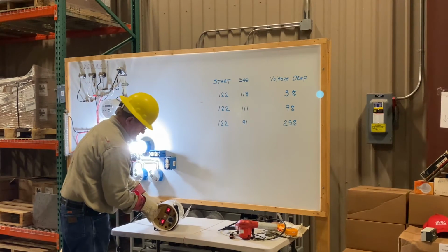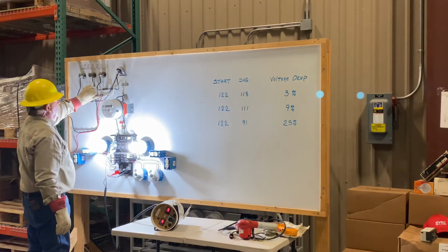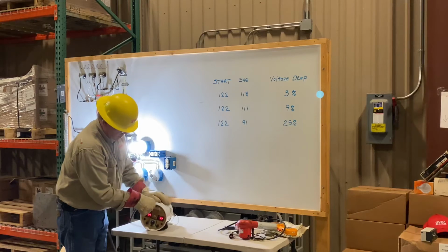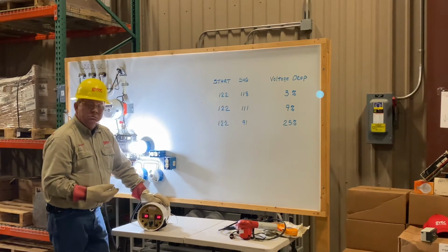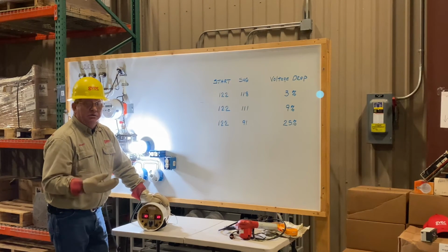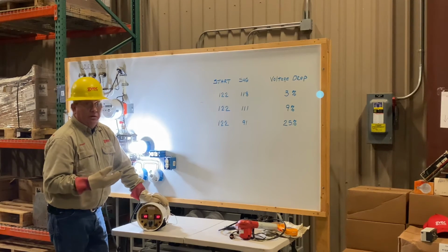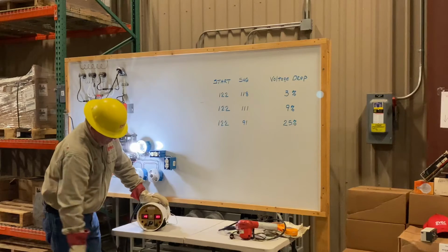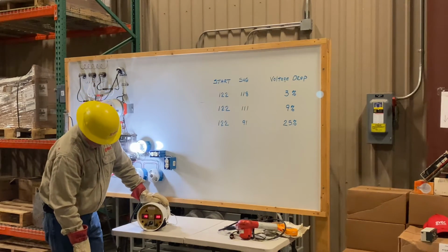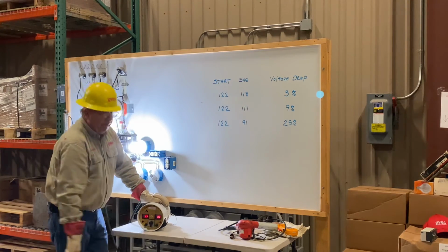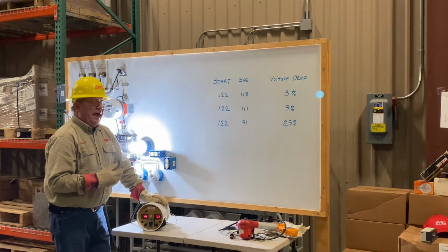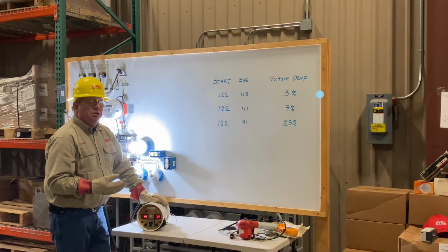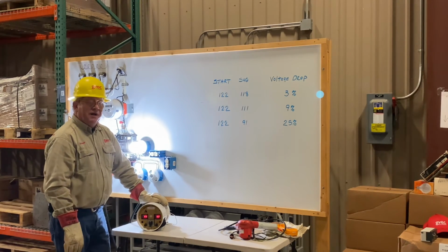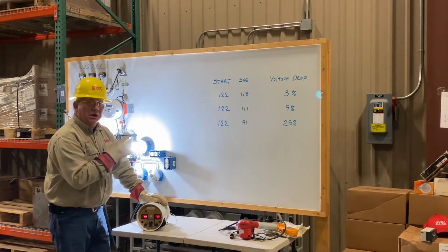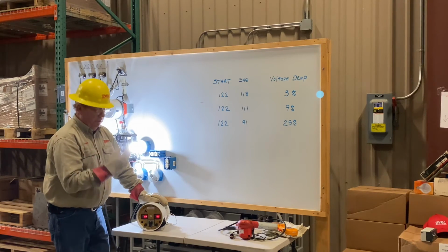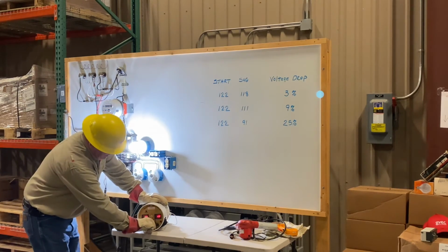So now we're going to go and create this resistive bad neutral connection. Right now we have a balanced load. We have a light bulb on the right, a light bulb on the left. They use the same amount of current. There is no current on the neutral, and we don't have a neutral problem. The Super Beast added that load to one side. The voltage on the loaded side fell to 90 volts. 90 volts is a 25% voltage drop. And if you see how dramatic it was in the light bulb, the other one, that voltage went up. We're going to do it on the left-hand side now.